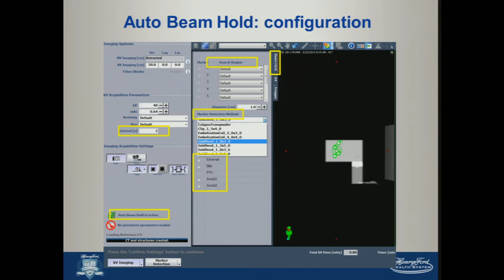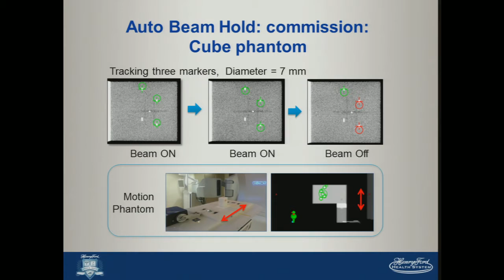So this is an example of how we commission the system. Shows it pretty clearly. We've got a moving stage here where this phantom with several implanted BBs is moving in the supinf direction. And we've indicated these green circles as the regions we want the markers that are detected by the auto beam hold software to stay within. So as long as all the markers are within those circles, the beam stays on. When one or more of them moves outside, which you see on the panel at the top far right, two of the circles have gone red because the detected markers have moved outside your tolerance radius there, the beam's held off.